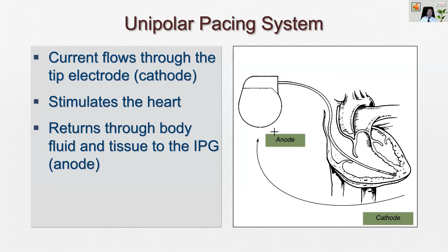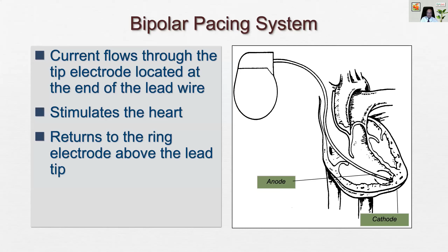more chance of interfering with the pacemaker function if it is unipolar. On the other hand, the bipolar pacing system has both the leads very close to each other in the pacemaker lead itself. So it has a tip electrode, which is the cathode, and it has a ring electrode, which is the anode. So the current circuit is very small, and therefore the chance of the electrical circuit being disturbed by external stimuli, cell phone radiation or other sparking radiation, or muscular activity, is very less. And that's how the leads look like.